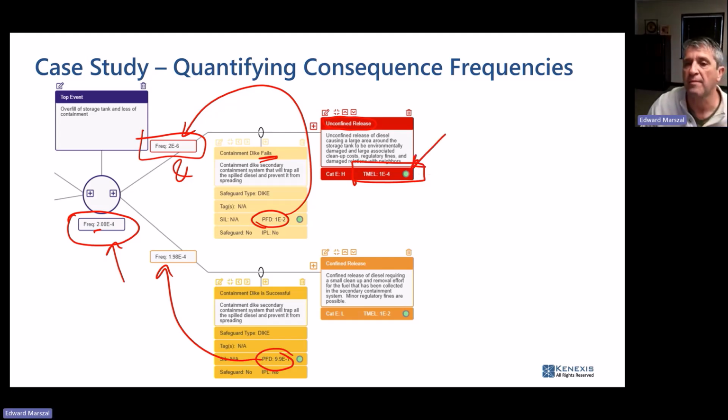Risk is tolerable. And you need to repeat that analysis for every potential consequence that you can come up with. So in the early stages of a risk analysis of a project, it's very possible that one of these consequences is green lighted, but the other one is red lighted, and that's not okay. I need to make sure all the consequences are green lighted in order to make sure that risk as a whole is going to be tolerable.